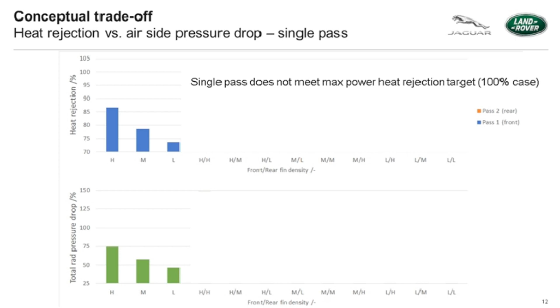So we then consider a twin pass configuration, and here we're looking at a high fin density radiator as the first pass at the front, and then different options for the second pass: a high fin density, medium fin density, and a low fin density. And here we see that the heat rejection performance is being met, so we can unlock that peak electrical power capability from the stack. And we also notice that the front radiator is doing most of the work, in excess of 85% here, for example, and the second pass is doing the rest. But also we see a ratiometric increase in the airside pressure drop, so we see the penalty starting to come through on the air side.